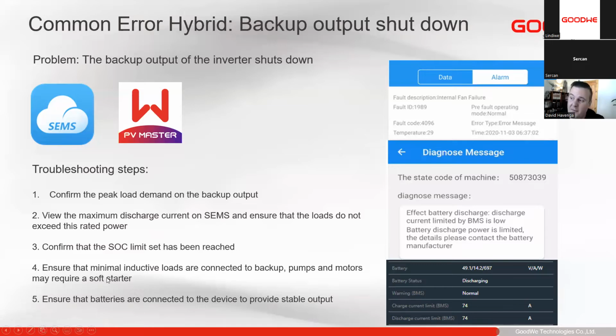Then we can also look at what type of loads are running. Sometimes we can't see the load that causes it to shut down, especially if it is inductive loads, motors, pumps, anything like that. Unfortunately, inductive loads are very evil loads because when they start, they can draw anywhere from 3 times to 12 times the rated power on startup, especially if they are getting older and aging motors or fridges and things like that. Sometimes they do unfortunately start to draw that 6 or 7 or 8 or 10 times the rated power on startup, and that over time can cause issues for the backup of an inverter, especially when we only have batteries available.